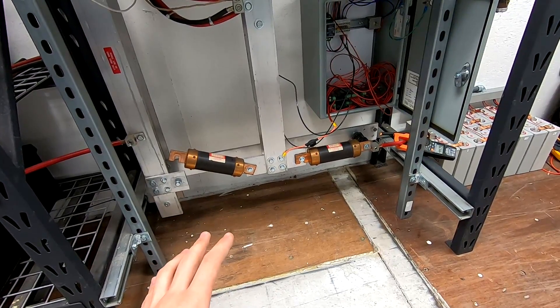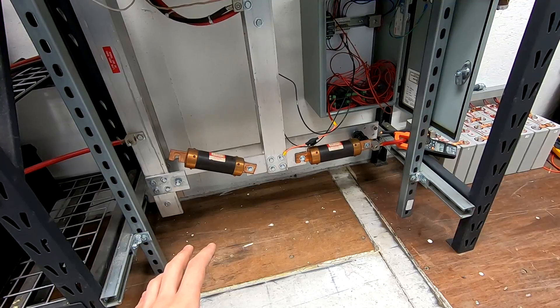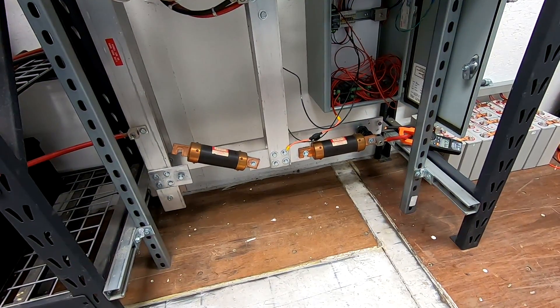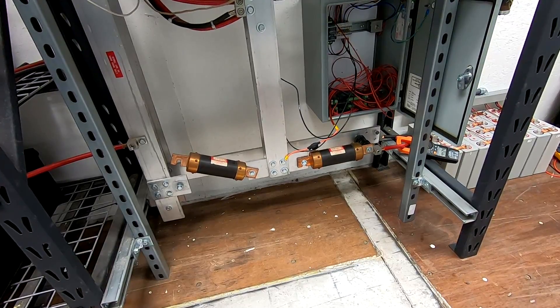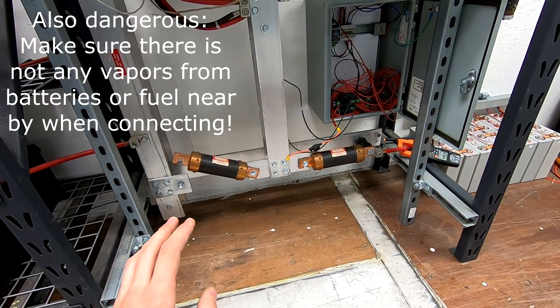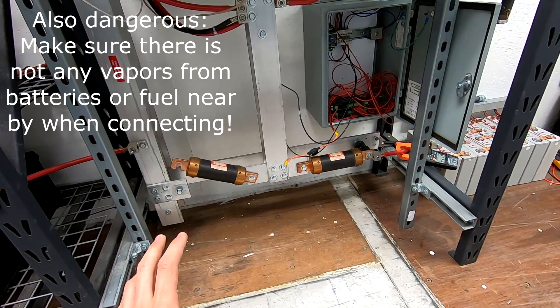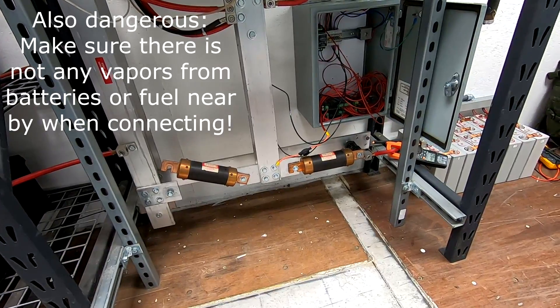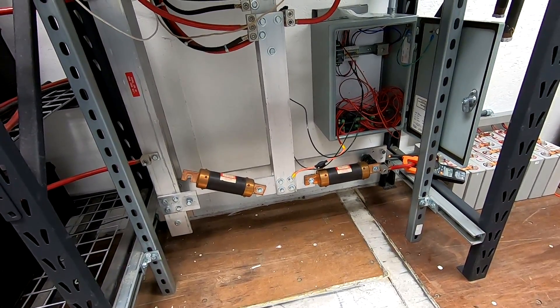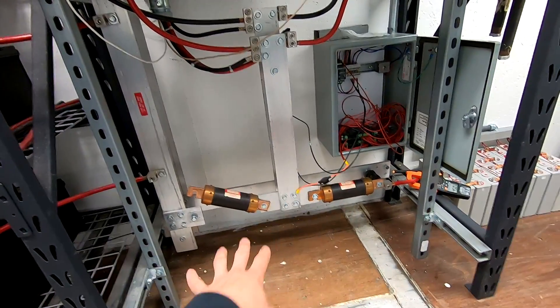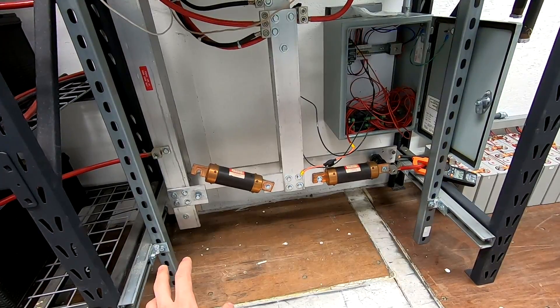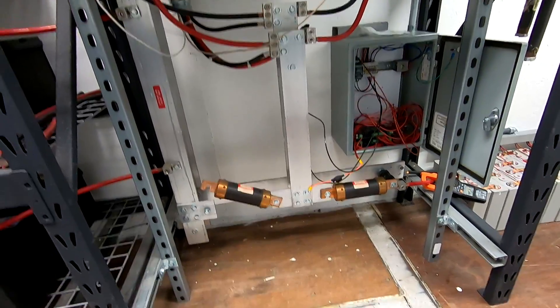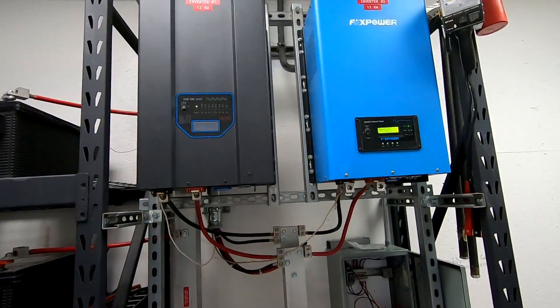Now I will say, you gotta be very careful, and wear gloves, and gear as if you're preparing for an arc flash, because there could be on your first connection some arcing, so be ready for that. This is definitely something that's dangerous and requires an experienced user, just because of the fact that there is no real off switch on batteries, and there's that potential for arcing. So then, like I was saying, you can charge on the lead acid, connect on the lithium, they're okay for a few minutes on the same bus, as long as you're not charging or discharging them, and then you can disconnect the lead acid, and now the inverters are running perfectly fine.